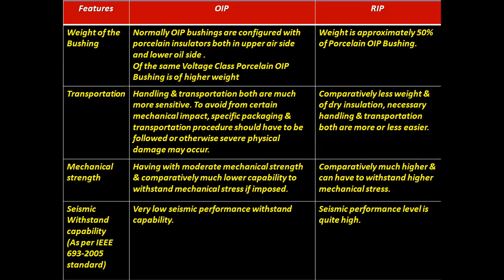Seismic withstand capability as per IEEE 693-2005 standard: OIP has very low seismic performance withstand capability. Seismic performance level is quite high in the case of RIP bushing.